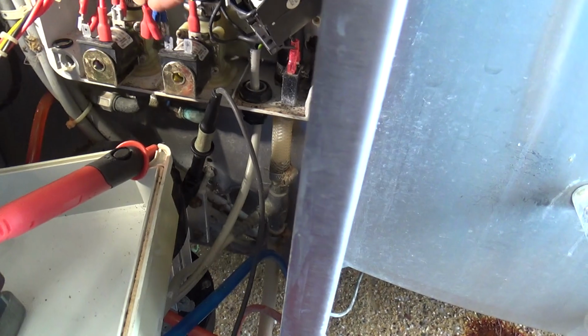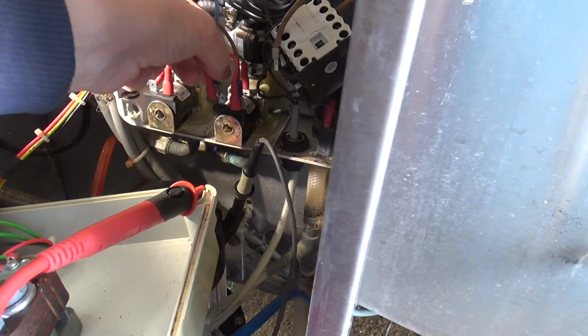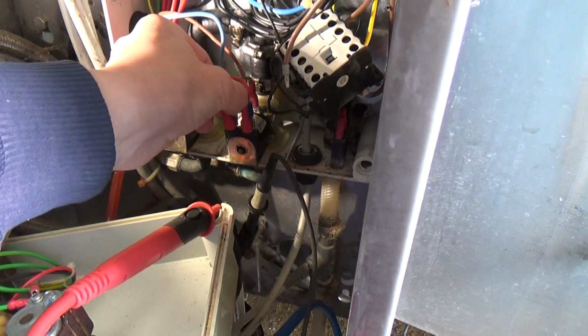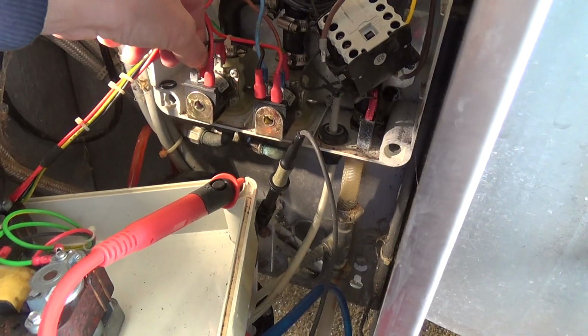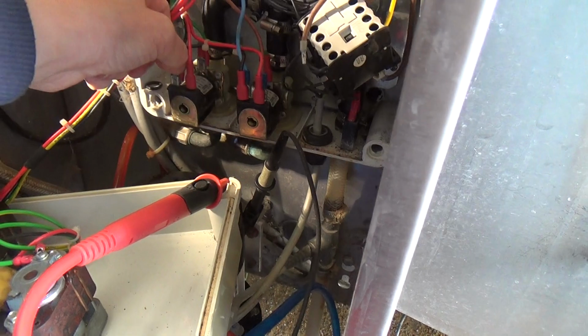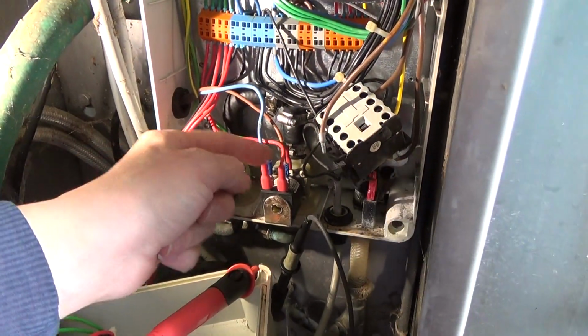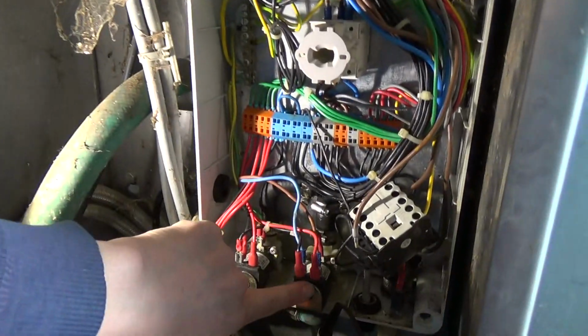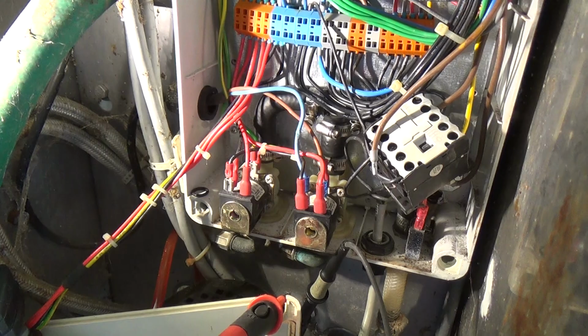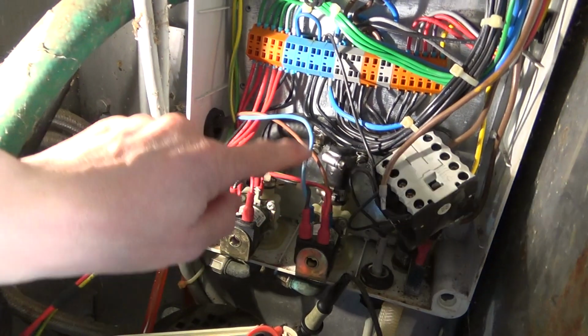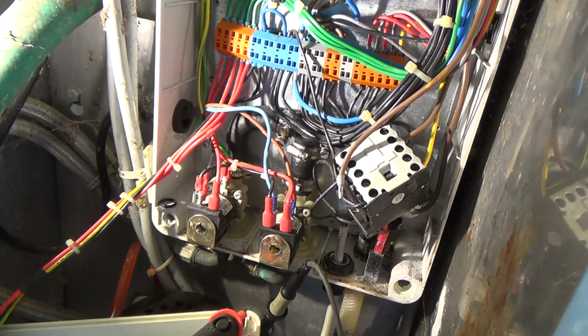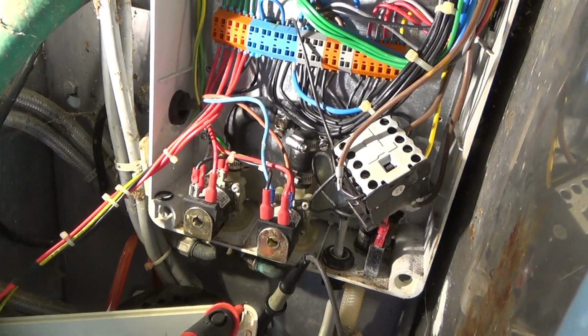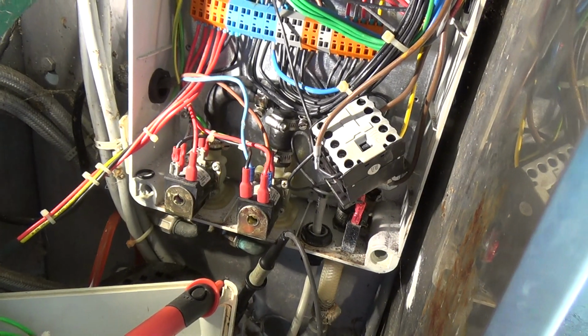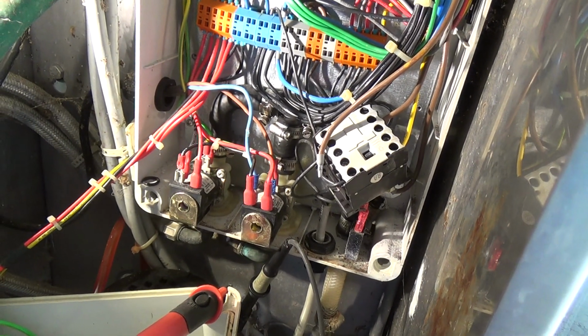So we have probably got a pump somewhere piggybacked off of that live feed to that coil, because we've got an extra wire piggyback. That brown wire, that pump, yeah, that goes up to that pump up there. So that's probably the hot water coil. So that is that, and they've piggybacked the neutral off of there as well. Yes. So that's an idea.